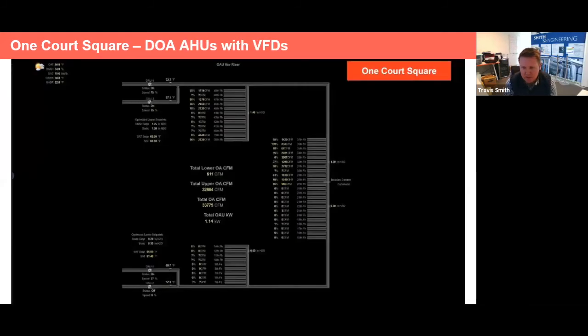Virtual airside economizer. So what we did here is you can't do airside economizer because you can't get 100% outside air to each of the air handling units. So we drive the temperature sometimes lower than design temperature from these DOAS units to kind of function as a virtual airside economizer. We put VFDs on all 4 of these DOAS fans, and they do a static reset based off damper position to each floor.